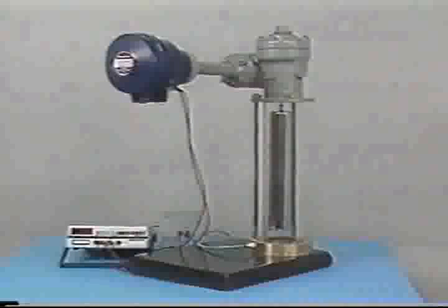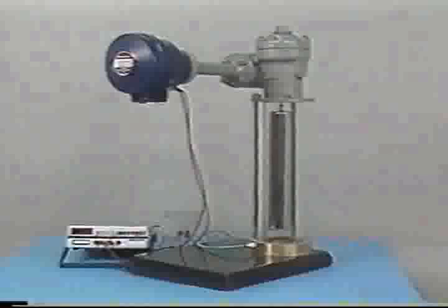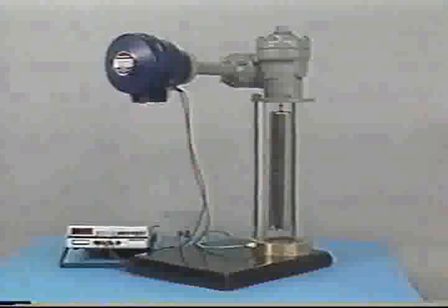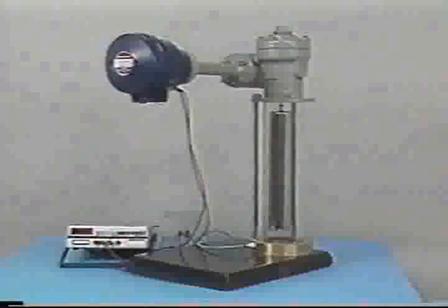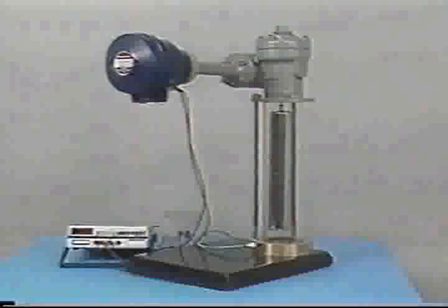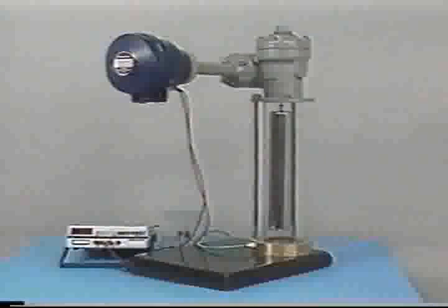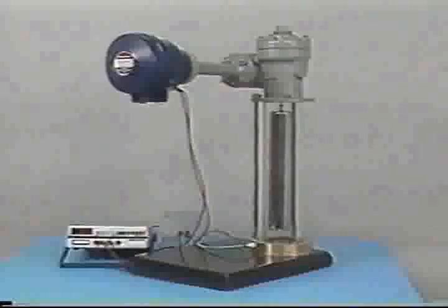We've also seen that, although the test equipment varies according to the instrument under test, zero is always corrected for the low-range value and span for the upper range. Adjustments are made and often readjusted until the instrument is properly calibrated.